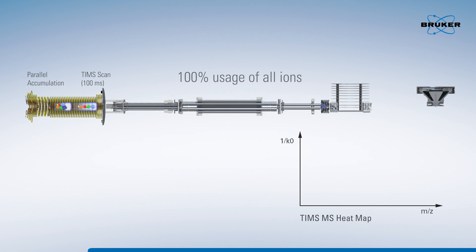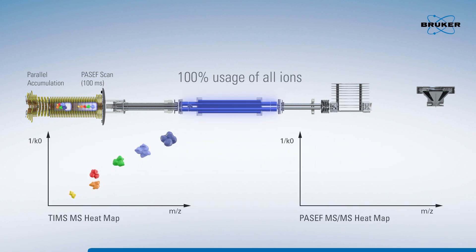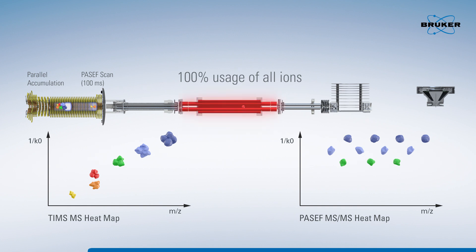The TIMSTOF Pro uses a dual TIMS device to accumulate ions and separate them according to their mobility. The ions are released from the TIMS region by ramping down the voltage in 100 milliseconds. The mobility peaks are just a few milliseconds in width, yielding a revolutionary increase in speed and sensitivity. The next batch of ions is simultaneously accumulated in the first TIMS region, resulting in a nearly 100% duty cycle.